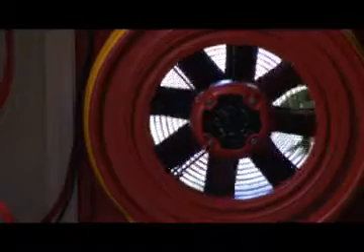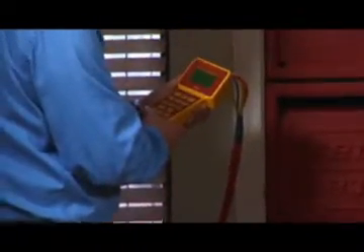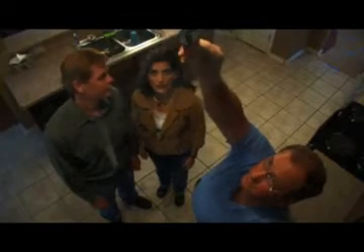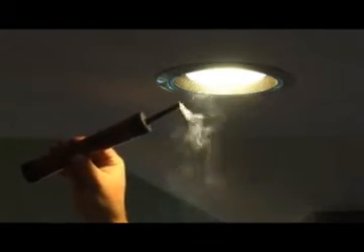The infiltrometer sets up in an outside doorway and creates a temporary pressure similar to a 15-mile-per-hour wind on all sides of your home to find hidden leaks. It creates a great visual opportunity to find the air leaks in the home. So we go around with a smoke puffer and homeowners see firsthand, wow, look at all that air going through that recessed can. Recessed lights in upstairs attics are big culprits and huge air leakers.